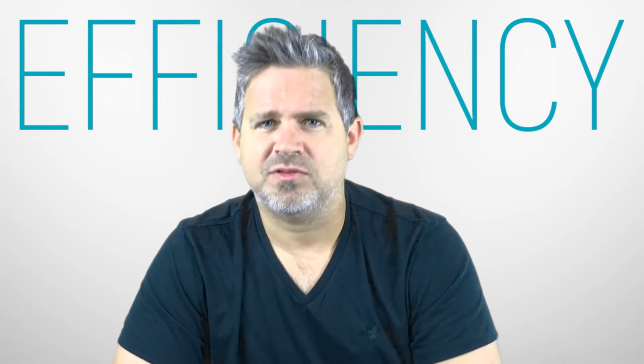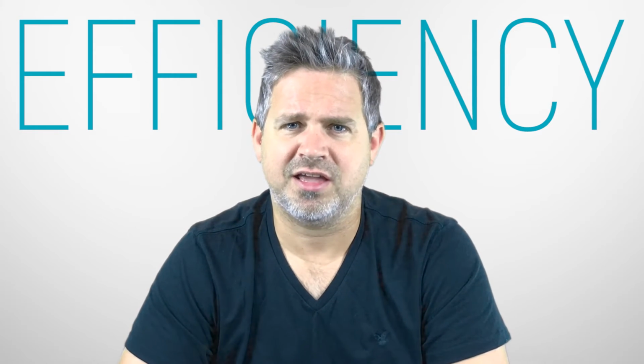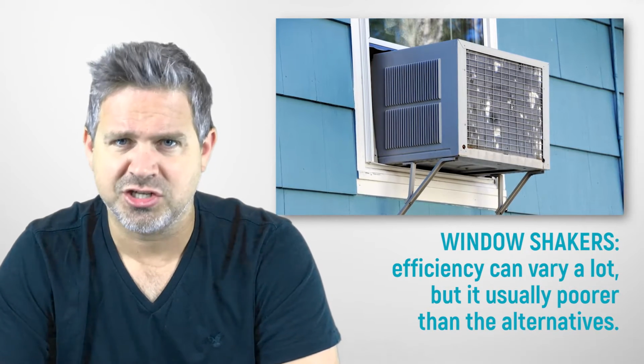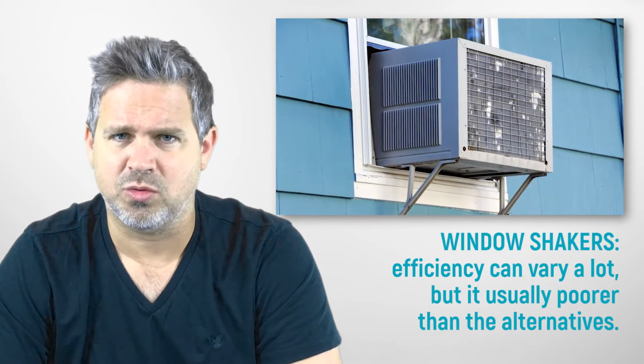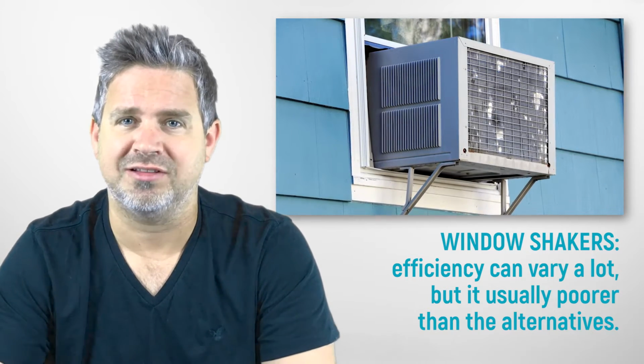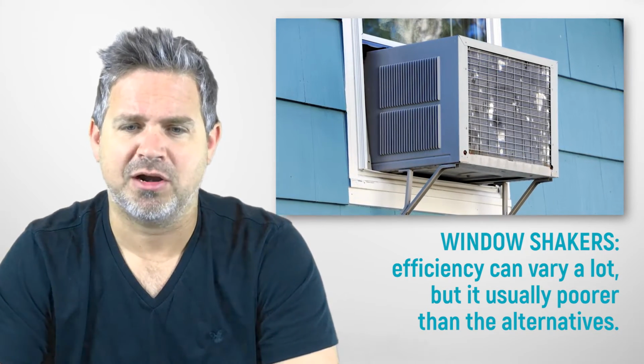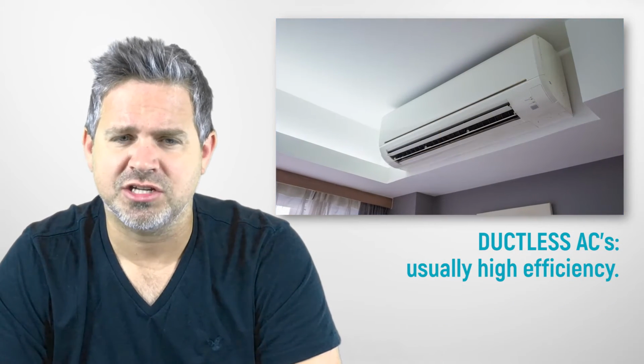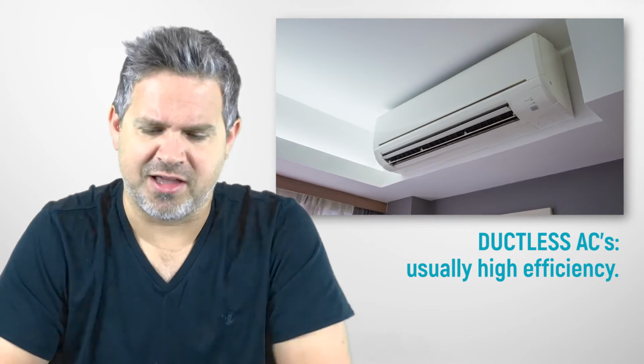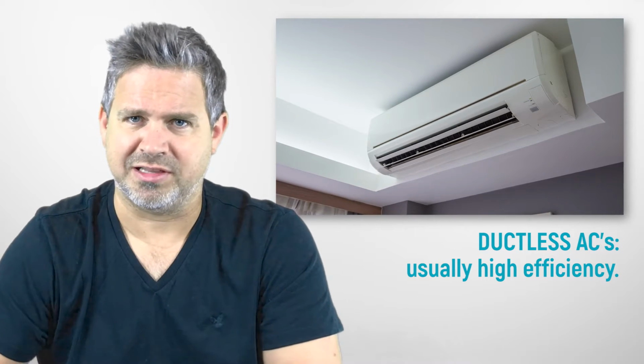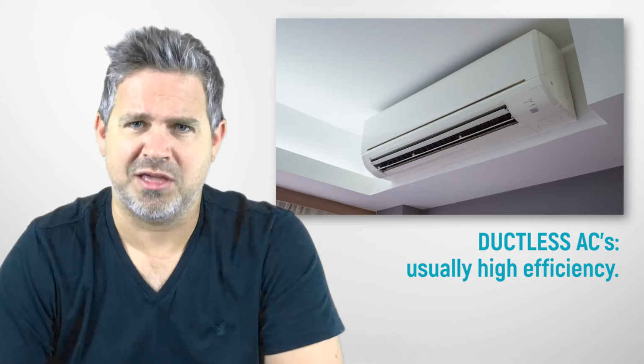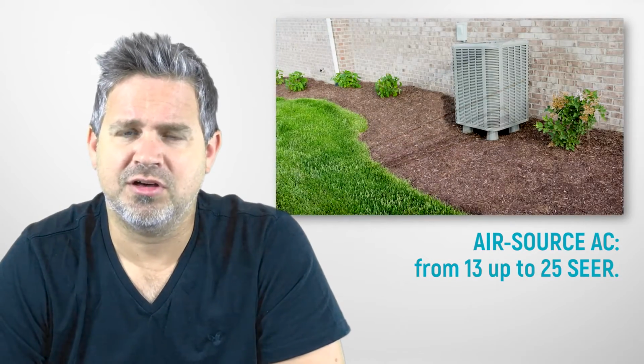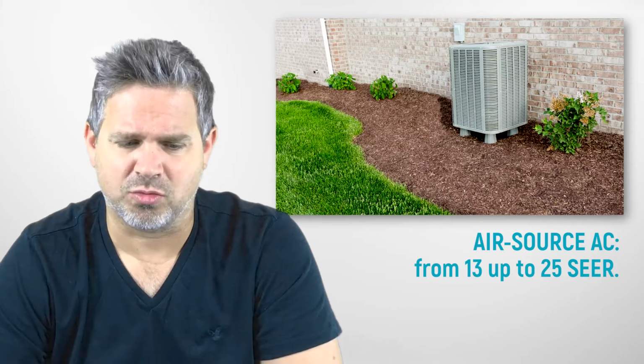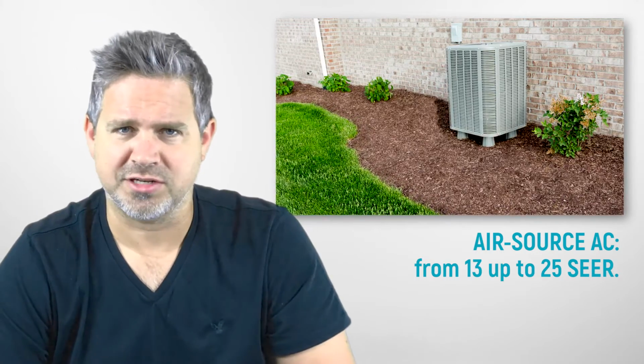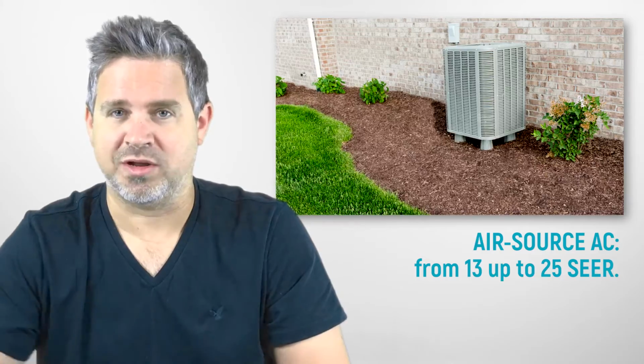So efficiency. That's the other part of air conditioning units that you need to consider. The efficiency of a window shaker air conditioning unit, they range, but a lot of them that are sold are lower efficiency just because they're a lesser expensive model. You can get better ones. For a ductless air conditioning unit, the efficiencies I find are generally a lot of times a little bit higher just because they can make them more efficient somehow. The whole house air conditioner, again, you can install the whole range, but it goes from, say, a low of 13 SEER up to a high of 25 SEER and stuff like that.